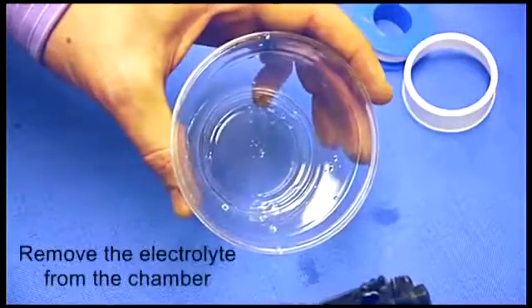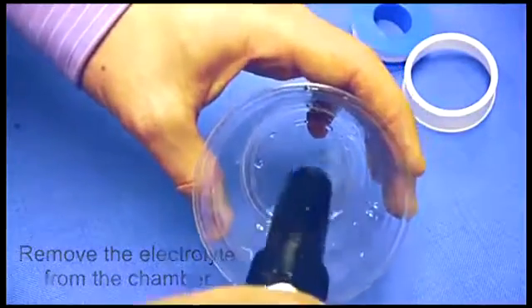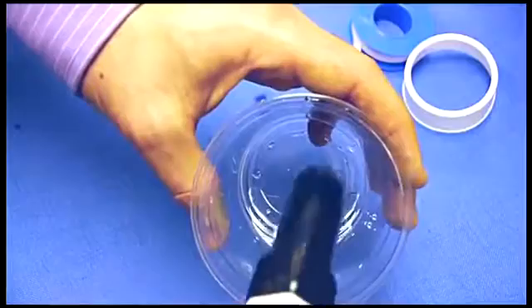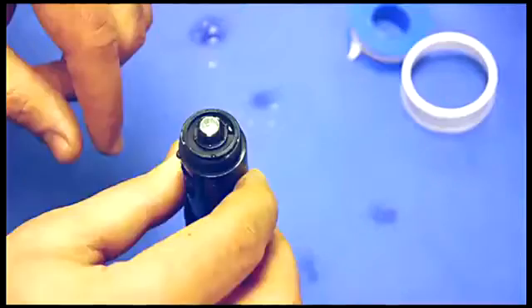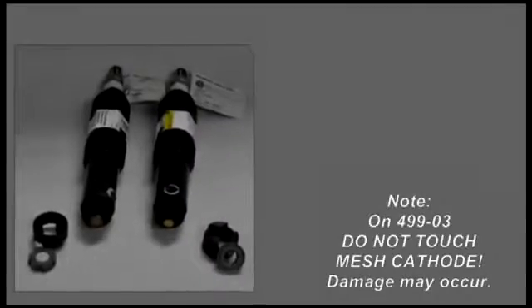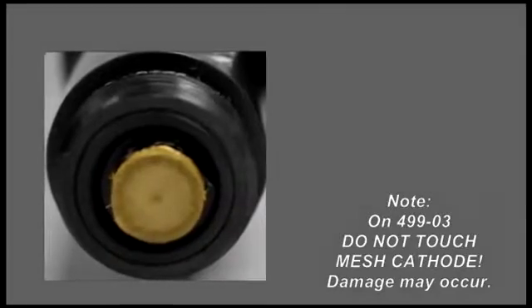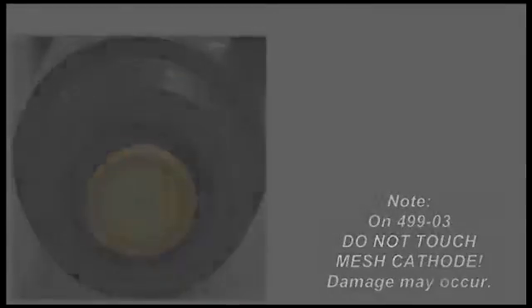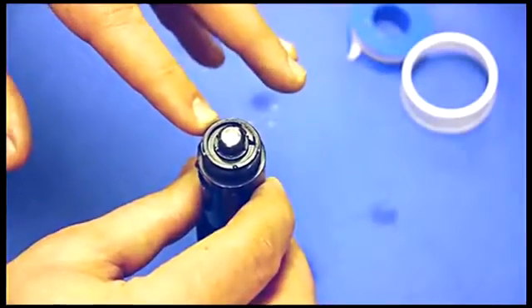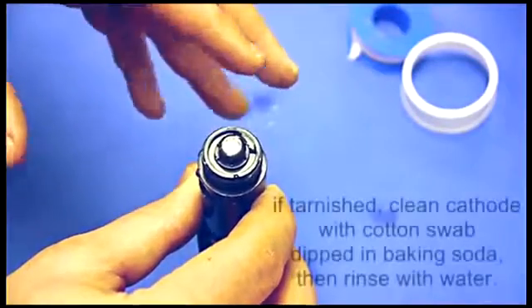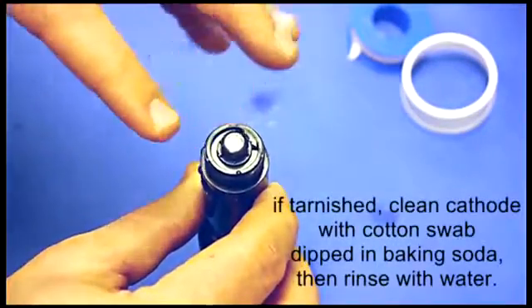Then you want to dump out the excess amount of electrolyte solution that's still in the sensor. Then you need to inspect the cathode. If it's tarnished, you just need to clean it with a cotton tip swab touched with baking soda and clean it off.